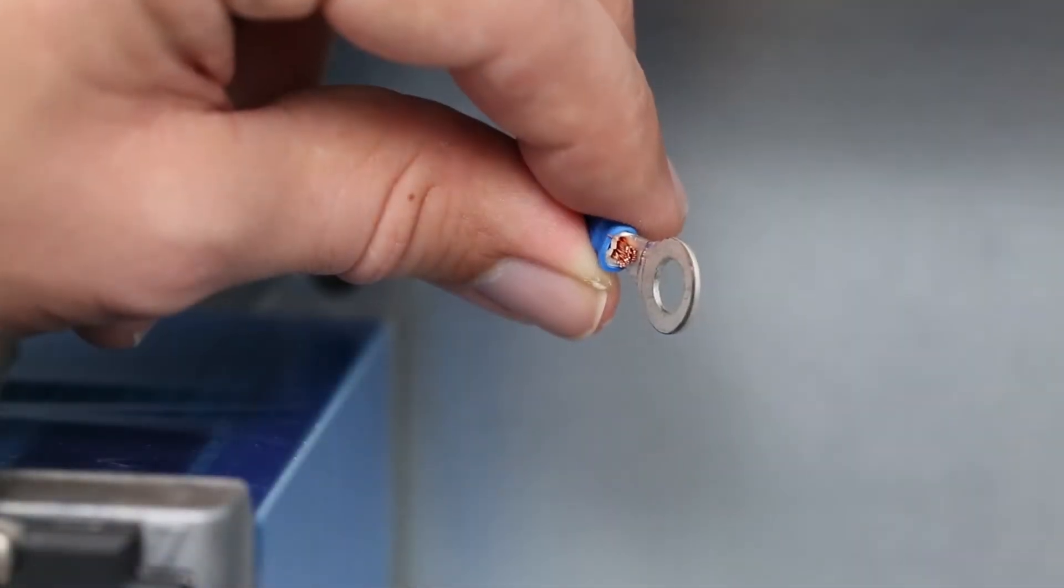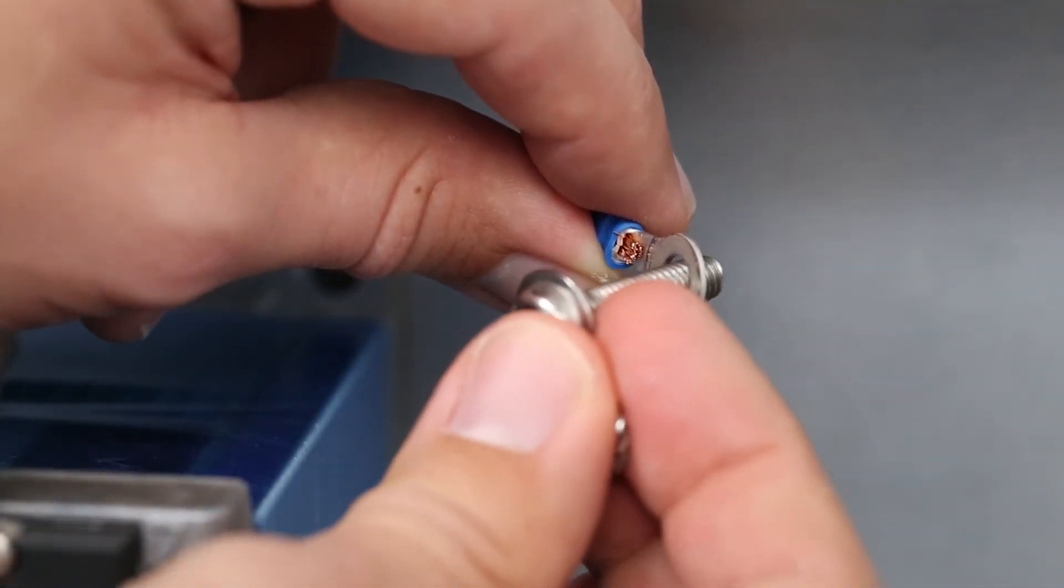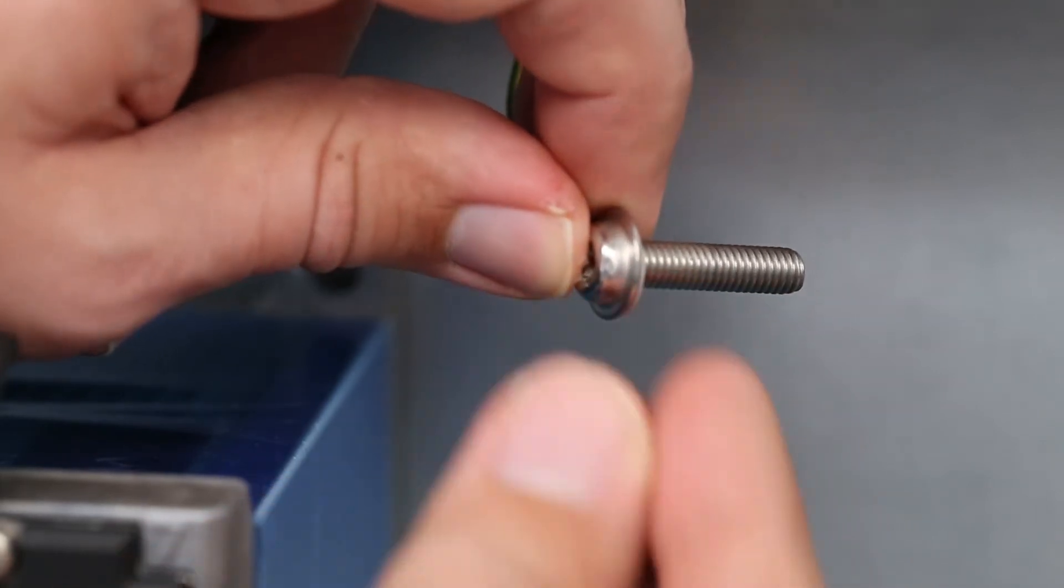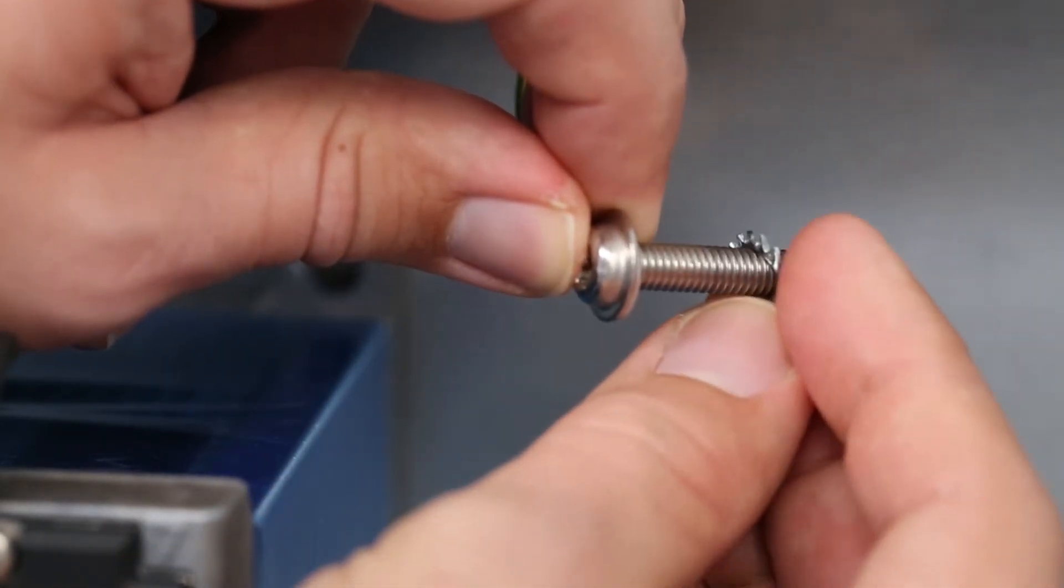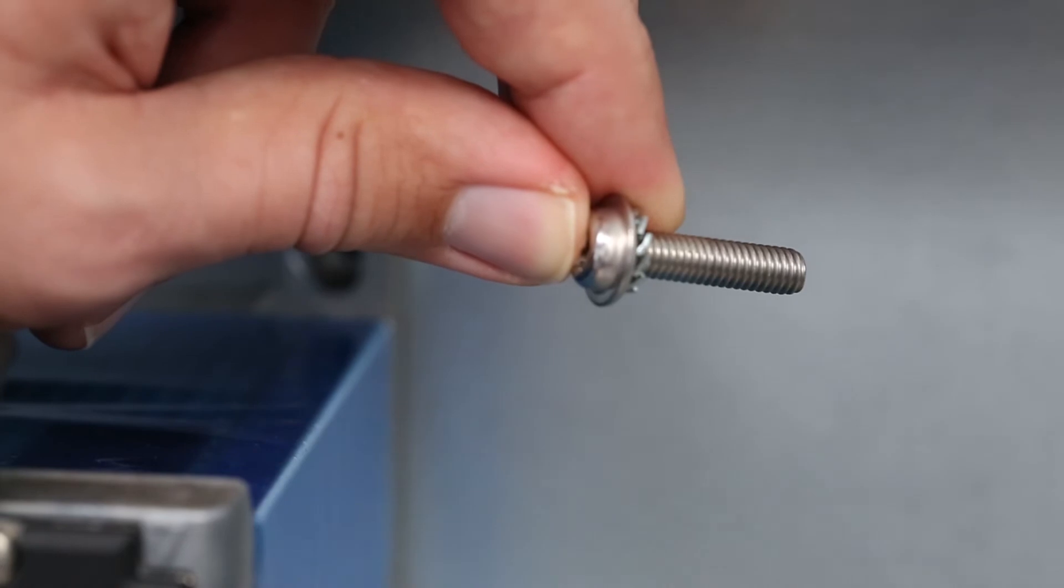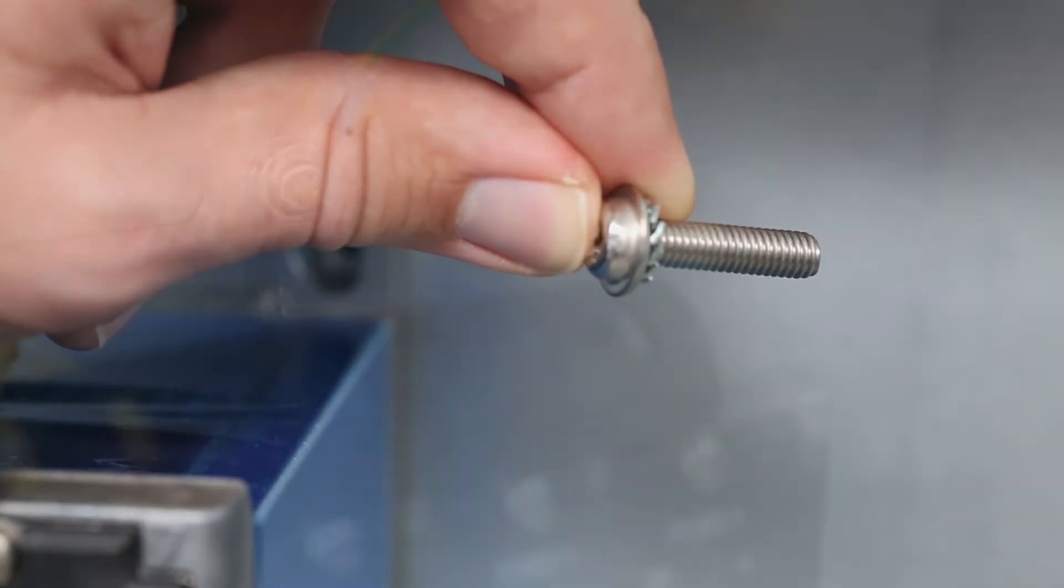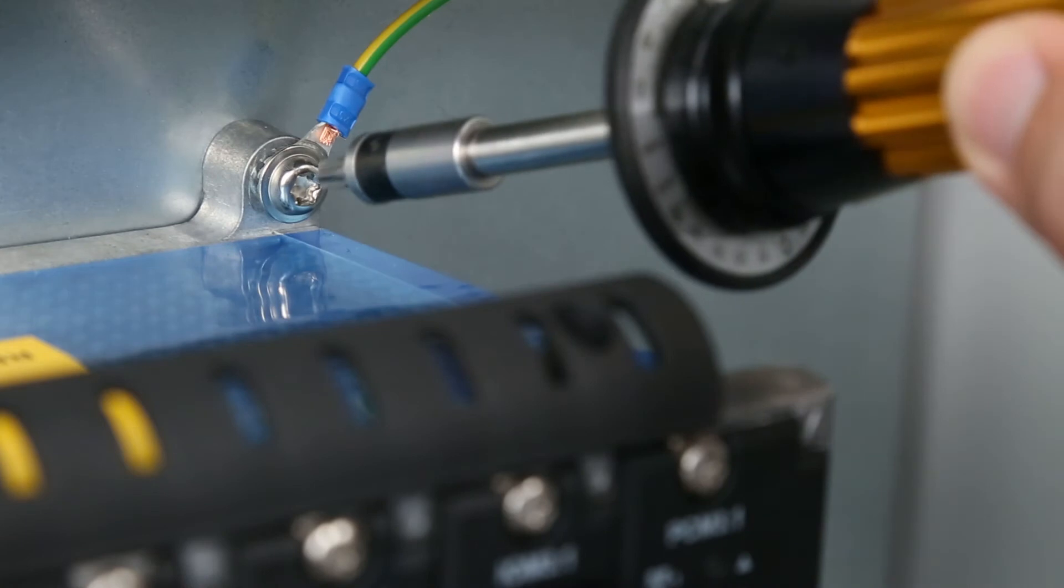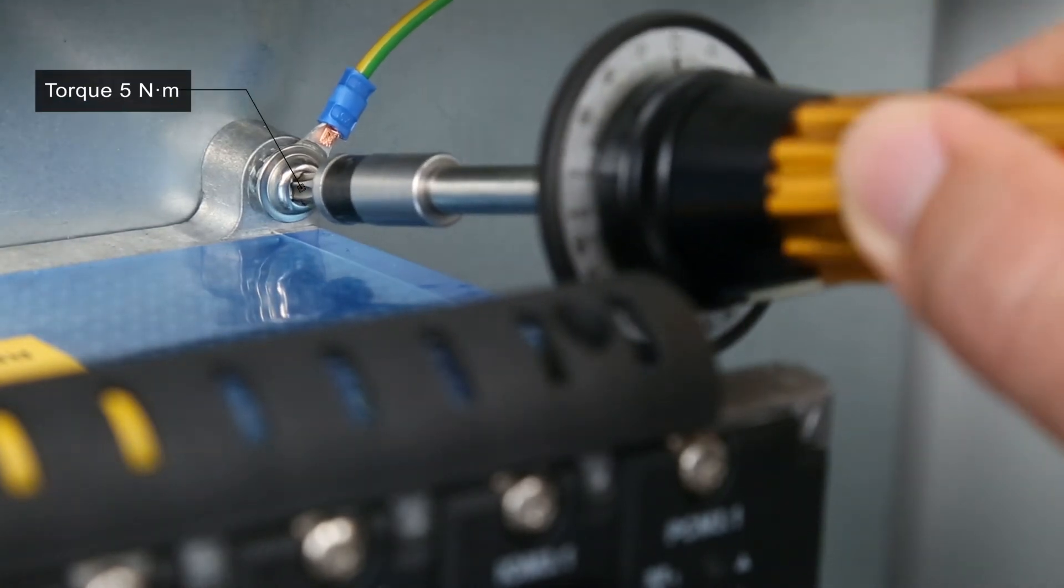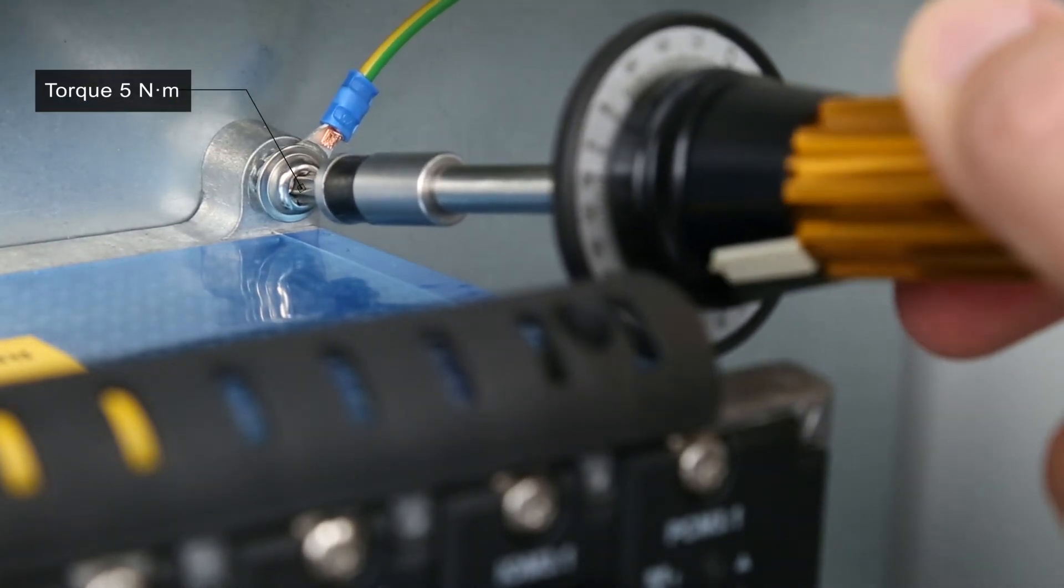The last fastener must be grounded to protective earth. Take the last fastener and place a grounding hoop onto it, then add a lock washer. Mount and tighten the last fastener using the correct amount of torque.